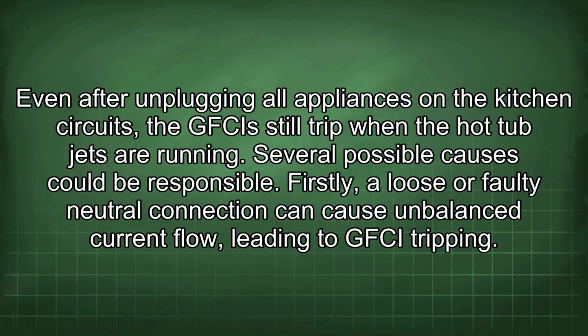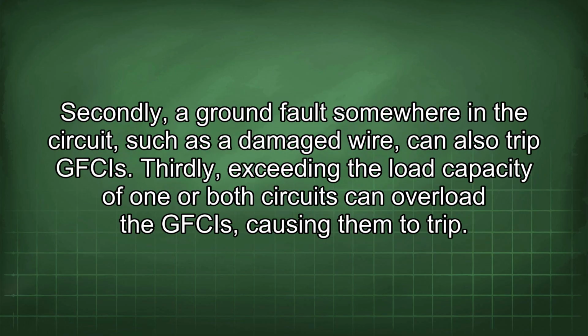Firstly, a loose or faulty neutral connection can cause unbalanced current flow, leading to GFCI tripping. Secondly, a ground fault somewhere in the circuit, such as a damaged wire, can also trip GFCIs. Thirdly, exceeding the load capacity of one or both circuits can overload the GFCIs, causing them to trip.